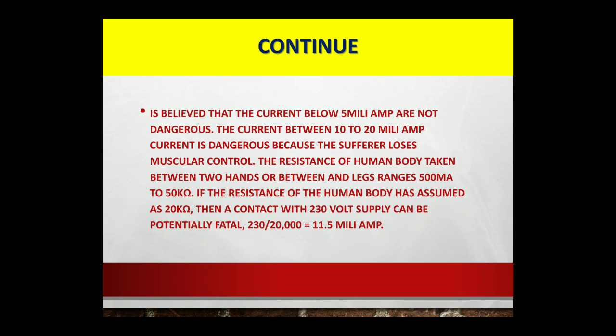If the resistance of the human body is assumed as 20 kilo ohm, then a contact with a 230 volt supply can be potentially fatal. That is equal to 230 volt divided by 20,000 ohm, which equals 11.5 milliampere. You can see that the current which is fatal for a human body is 10 to 20 milliampere. So whenever it is 11.5 milliampere, it is a very dangerous current for a human body.